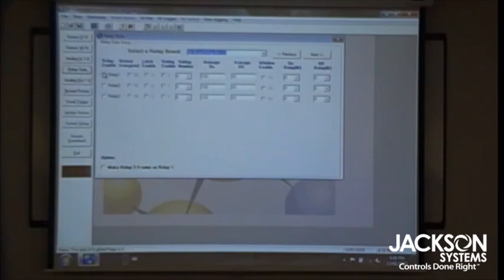Relay style, it has 3 relays on board. You can choose normally energized, so basically your relay is closed and you have current going through it. You can have that in fail-safe mode, so if you're operating a device that needs to be shut down when the power is shut down, it'll open when the power's turned off. You can have latched, you can have voting.